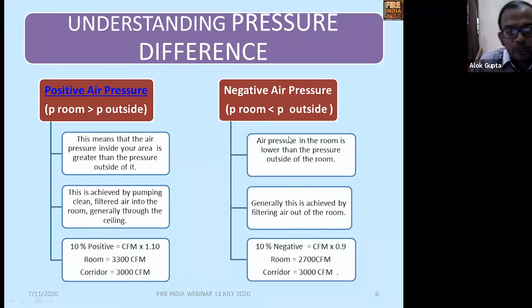So let's understand a little bit what smoke evacuation is as per NBC. A smoke evacuation system works through multiple exhaust grills located on each floor and connected to vertical risers in the shaft. Each grill will be provided with smoke dampers, which will open on sensing smoke, by the smoke detector in the corresponding corridors. And simultaneously, outside makeup air will be supplied. That's what I said in the last slide: we calculated 2800 CFM, and a similar amount of air we have to supply.